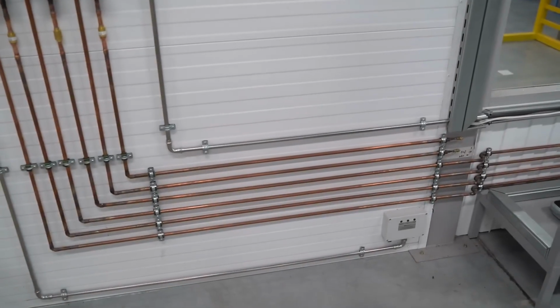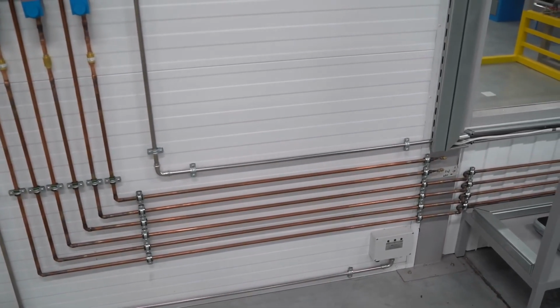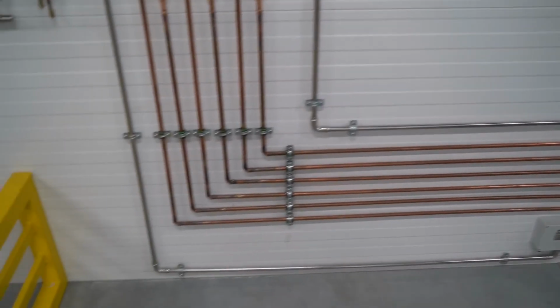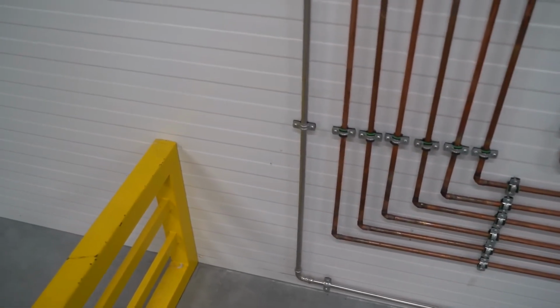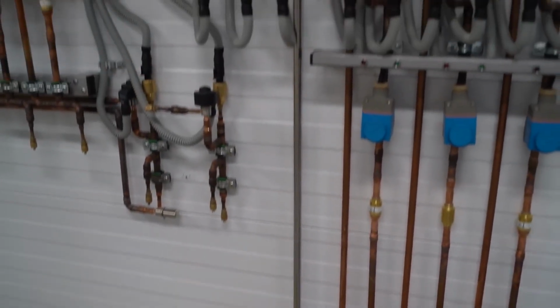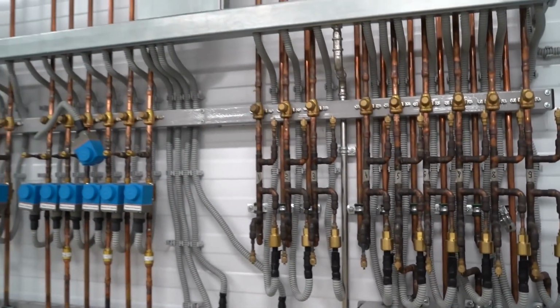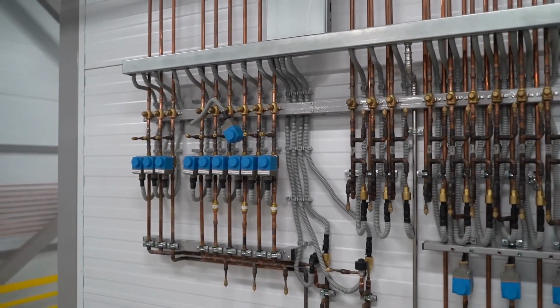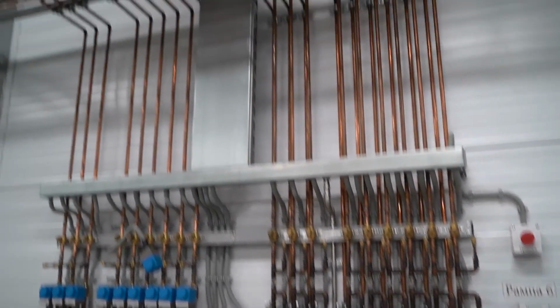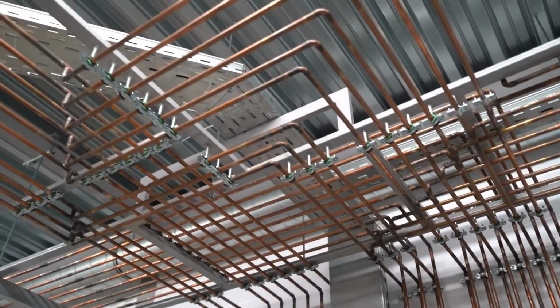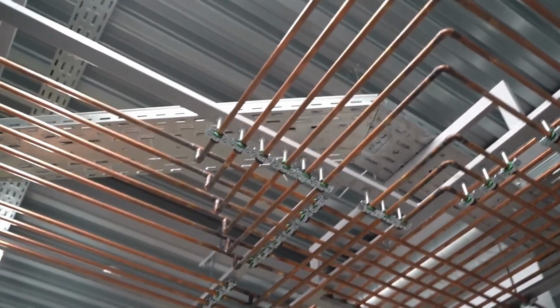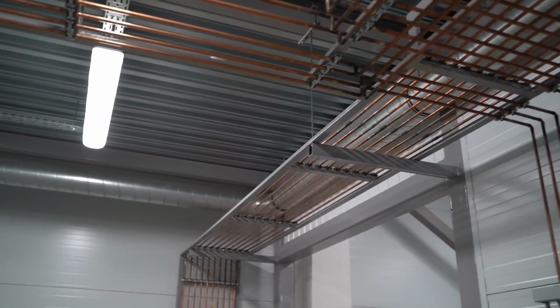Also, for safety reasons, even though refrigerants are not toxic, they can cause suffocation. We have gas detectors installed below. The refrigerant analyzers, which are important safety devices, are triggered by dry contacts at approximately 500 parts per million and also at 2000 parts per million. If either of these threshold levels is exceeded, an alarm will sound and the emergency ventilation system will be automatically activated to ensure safety. I think, of course, it's very unlikely that anyone would actually die from this situation, but just in case, safety always comes first.